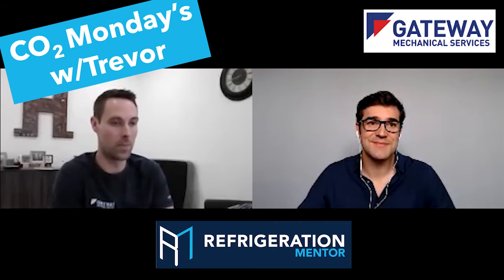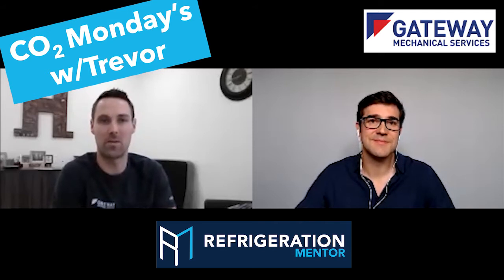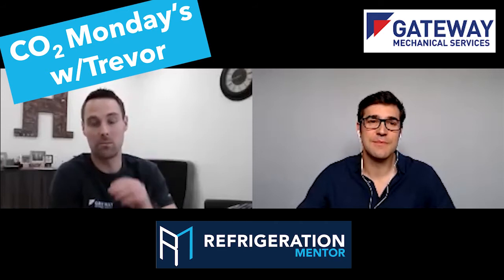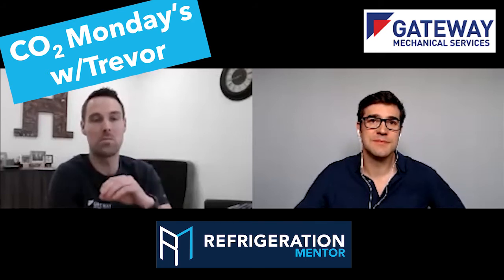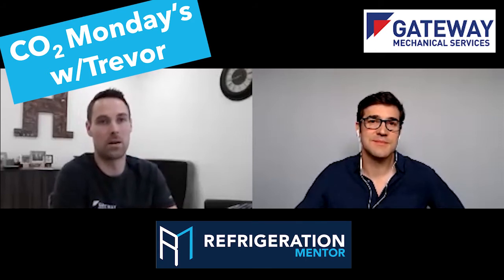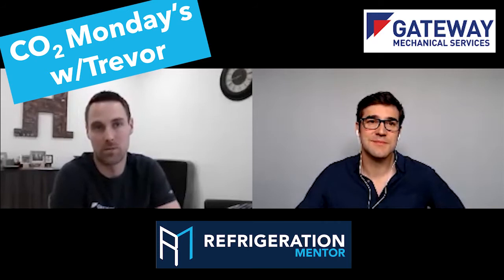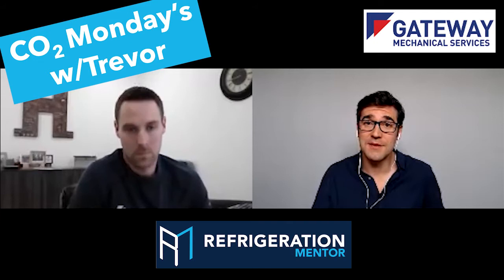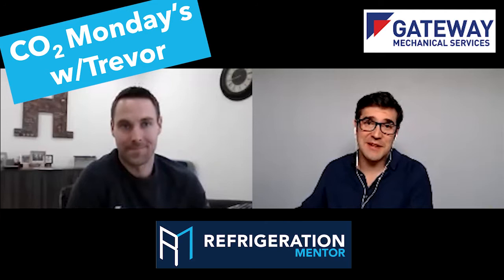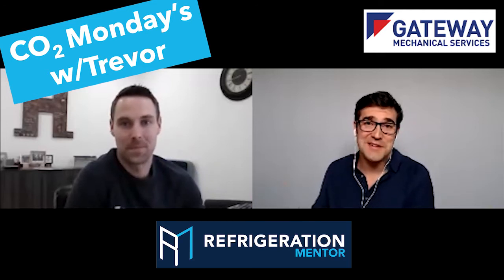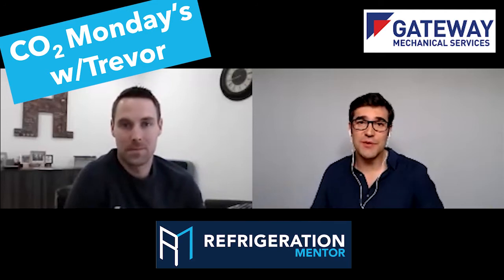So really the biggest thing, especially when you get into different rack manufacturers, a lot of things are going to end up being the same, but fully understanding that sequence of operation and how that rack is supposed to run will shine a big light on how you need to set it up and service it. Yeah, and that's so important. I talk about that a lot in the trainings I do. Understanding the sequence of operation, like you said, is so important, because one manufacturer's sequence of operation is probably a little bit different, even though it's all the same principles of refrigeration. So you really want to understand that.